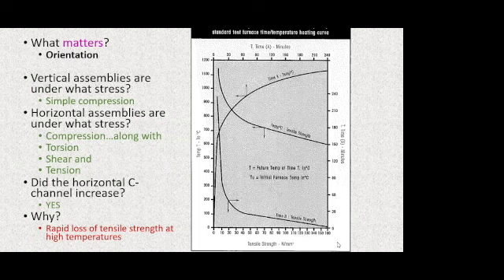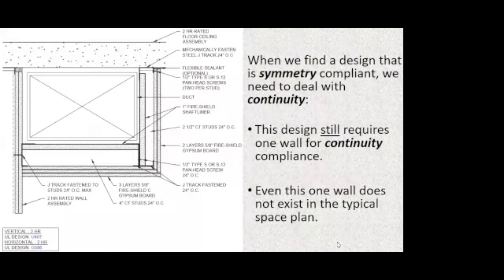And the sad truth is, at that 2 hour threshold, most manufacturers chose not to test the duct for 2 hours. They tested duct A 1 hour, duct B 1 hour. They went to 2 hours, they tested 2 hour duct A, and then suddenly, for some strange reason, they stopped testing 2 hour duct B. I can't say why. I just know from the testing that I've seen done that it's really hard to pass that test. And let's face it, if they're getting away with selling duct A for things that should be duct B, and they're not being held accountable for putting that compromised product design on the street in applications where it will fail, where it will not meet the intended fire exposures, they're likely to keep going.